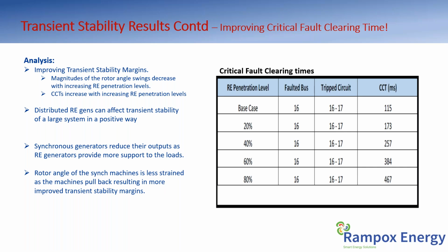Many other systems would still conform to that, depending on the type of breakers they use. If they're using the old 3-cycle breakers, they would have about 60 milliseconds to operate. If you look at your cycle in a 50 hertz system, a 3-cycle breaker gives 60 milliseconds, then add maybe 20 milliseconds flight time for your signals, and another 20 milliseconds for your relay. That gives you a total of 100 milliseconds.